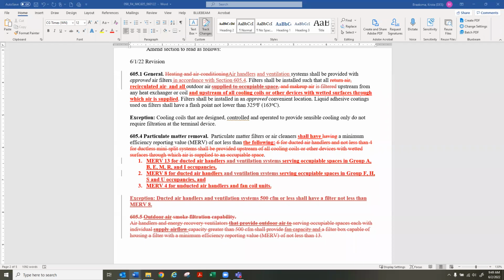As long as you're filtering the outdoor air once prior to introducing it, you should be good to go. So you might have a MERV 3 filter or something like that, or an unrated filter ahead of the heat exchanger for the ERV. And then you've got your MERV 13 filter downstream of that, but before you get to the cooling coil. In that case, you're saving energy because you don't have static pressure losses associated with two MERV 13 filters, and you're still providing the minimum protection required for the occupants. So I just wanted to make sure that we can still do that with this language as written.